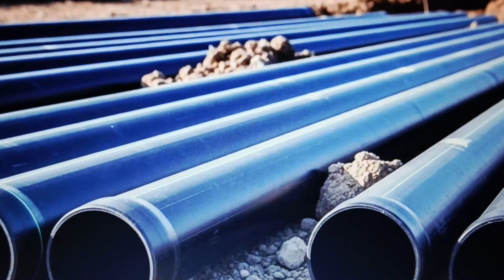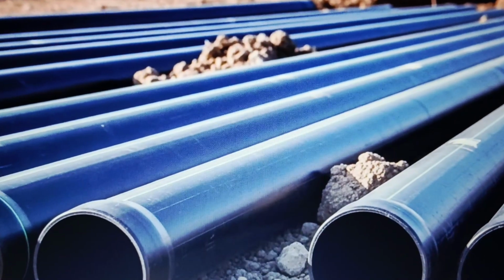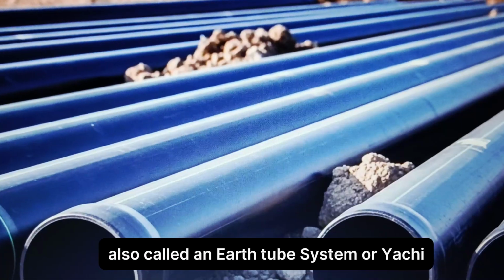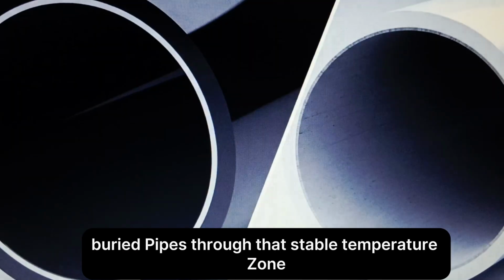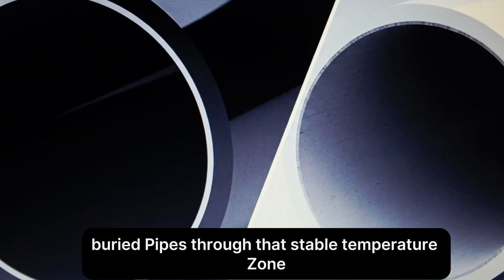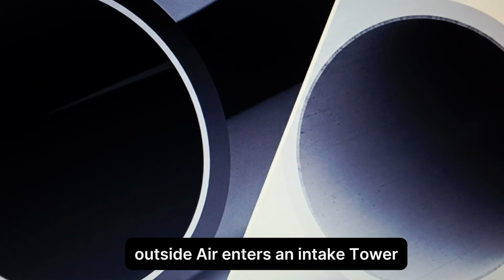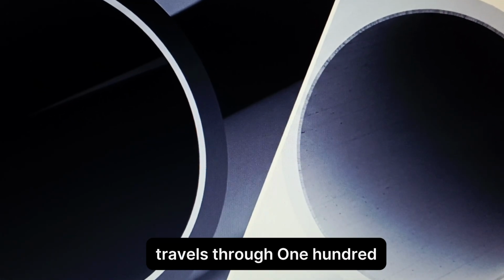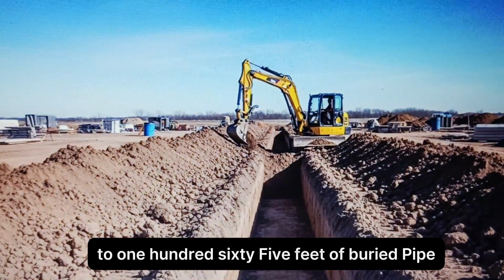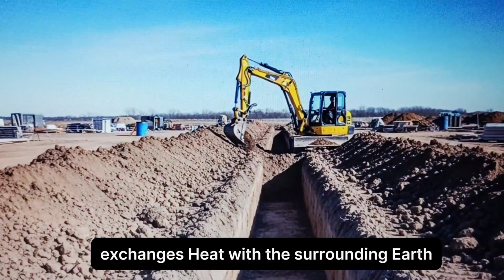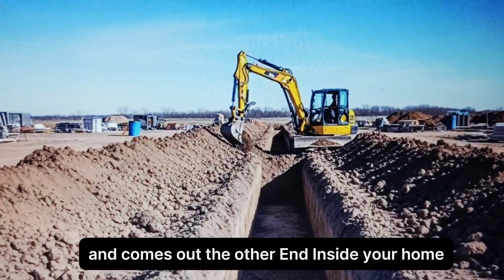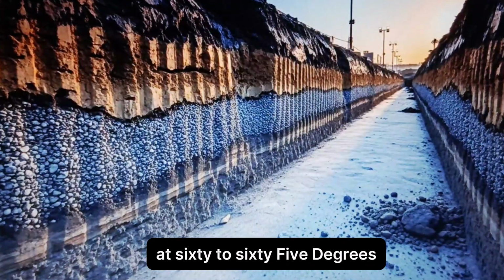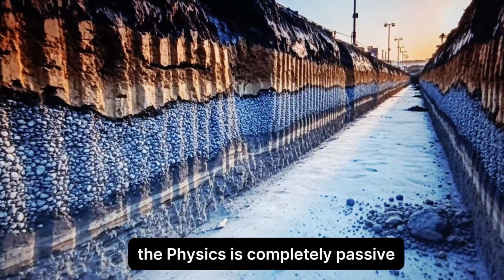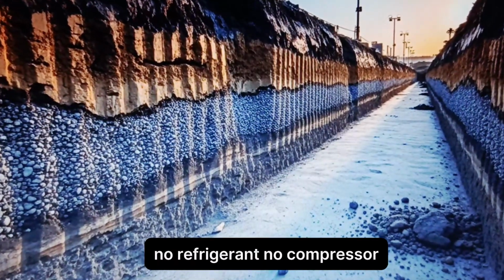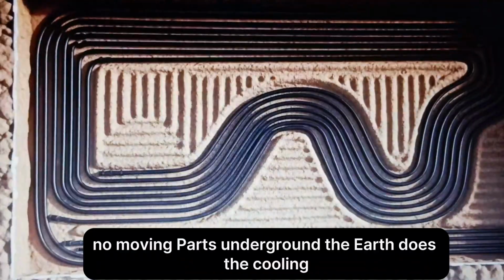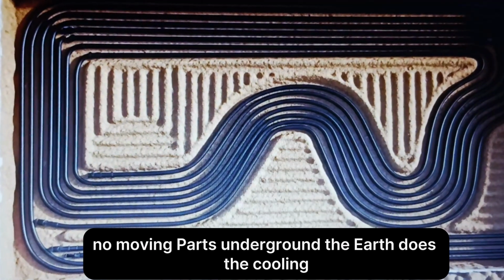It doesn't move. An earth-air heat exchanger, also called an earth tube system or EHE, works by running buried pipes through that stable temperature zone. Outside air enters an intake tower, travels through 100 to 165 feet of buried pipe, exchanges heat with the surrounding earth, and comes out the other end inside your home at 60 to 65 degrees. The physics is completely passive. No refrigerant, no compressor, no moving parts underground. The earth does the cooling.